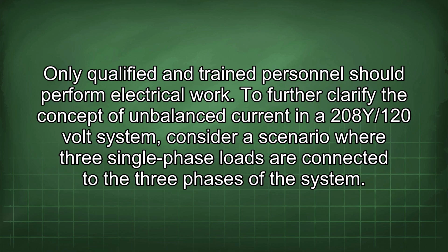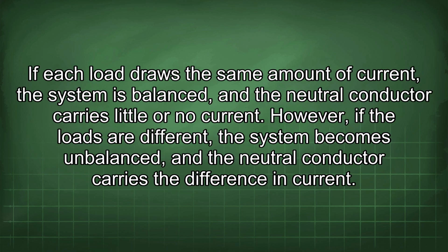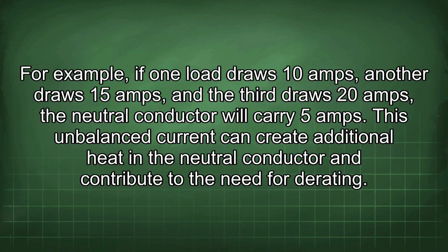To further clarify the concept of unbalanced current in a 208Y/120 volt system, consider a scenario where 3 single-phase loads are connected to the 3 phases of the system. If each load draws the same amount of current, the system is balanced, and the neutral conductor carries little or no current. However, if the loads are different, the system becomes unbalanced, and the neutral conductor carries the difference in current. For example, if one load draws 10 amps, another draws 15 amps, and the third draws 20 amps, the neutral conductor will carry 5 amps. This unbalanced current can create additional heat in the neutral conductor and contribute to the need for derating.